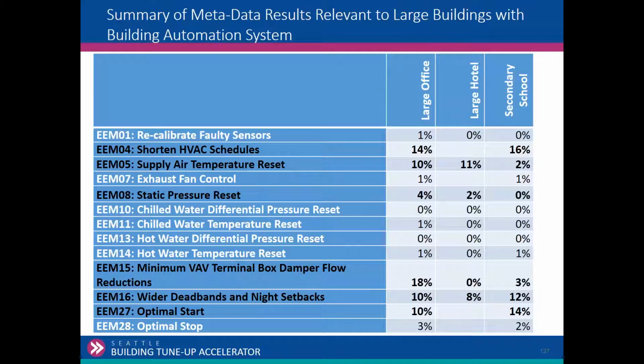Supply air temperature reset. Are they resetting supply air temperature at all? Maybe originally the design intent was to reset supply air temperature, but for whatever reason, they weren't able to meet their load. It was a humid day and they needed more dehumidification. Whatever was going on, they overrode the reset and never set it back in place. So do they have the capability for resetting?